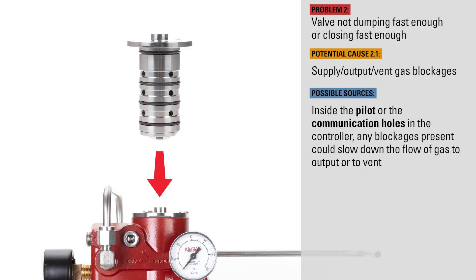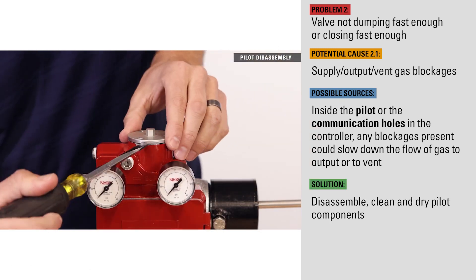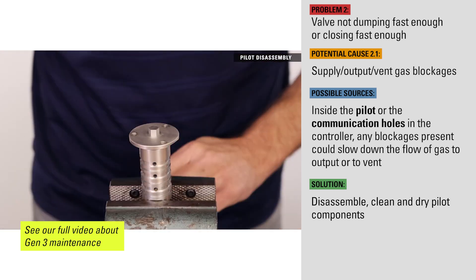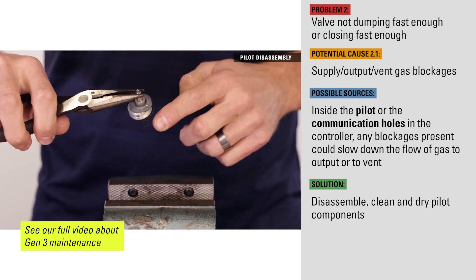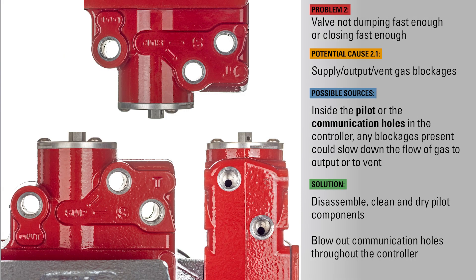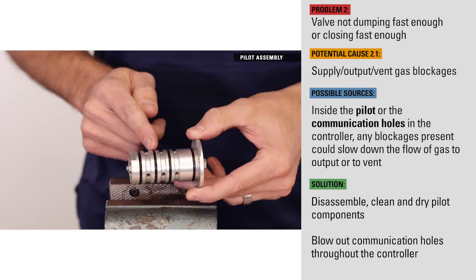Inside the pilot or the communication holes in the controller, any blockages present could slow down the flow of gas to output or vent, keeping the valve from opening or closing as fast as it should. To check for contaminants, remove the pilot from the controller and disassemble. Check for any solids or moisture. Blow out the supply, output, and vent communication holes throughout the controller to ensure they are clear. Clean and dry the pilot components before reassembling.